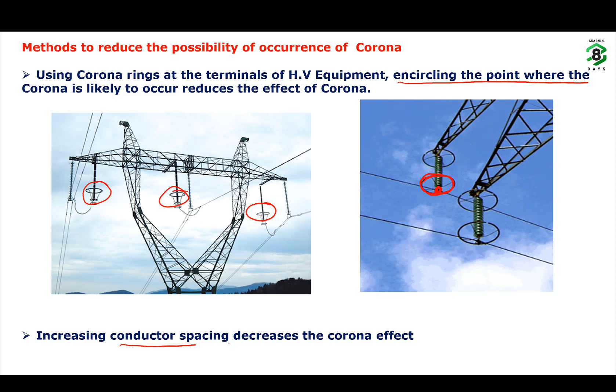So we are using corona rings at the terminals of high voltage equipment, encircling the point where the probability of occurrence of corona is more. You can see in this high voltage transmission line, corona rings are provided at the points where corona is more likely to occur to reduce its effect. Again, we have seen that increasing the spacing between conductors also decreases the corona effect, which we have already done. Now, factors increasing the possibility of corona.